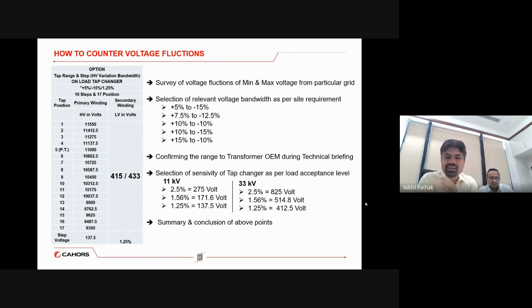But ideally, the situation of the last 5 years and today will have a tremendous difference in the loading of that particular grid. Many new users must have been added to the grid. Expansion happens, the loading differences, the voltage drops and the conditions change. So for any new customer, new expansion project or new facility development, we have to make a survey of the minimum and maximum voltage fluctuation level in that particular grid.